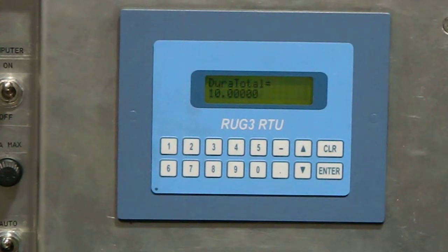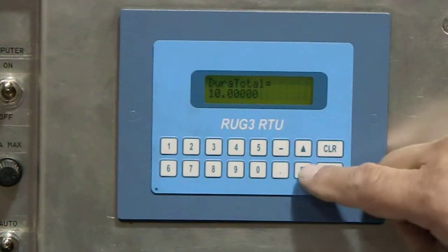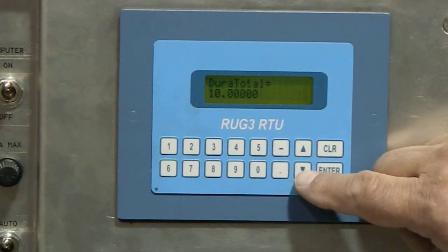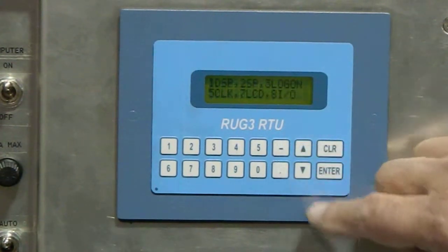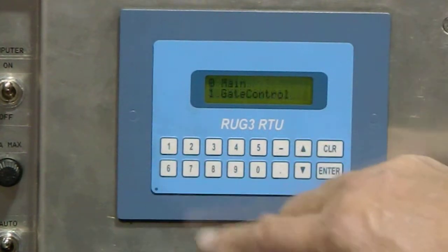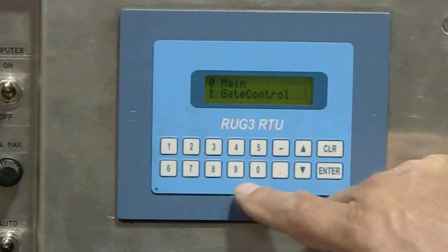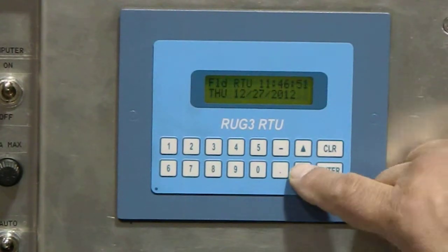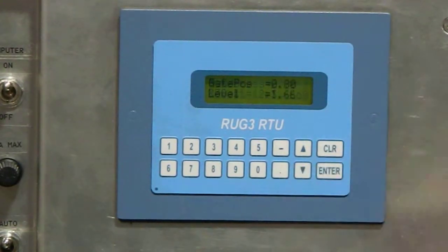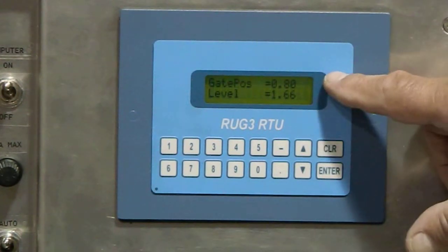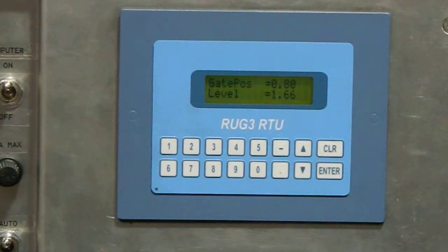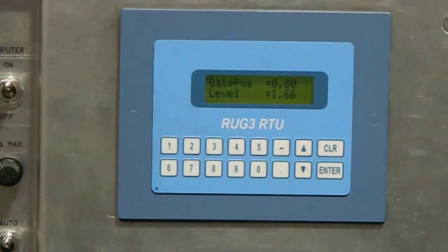Now, that's to give you 5 seconds of lag time. In most cases, it would be many more seconds than that to let the water adjust or to let whatever systems you have settle down before you want to make another adjustment. Minus gets you to the main menu. 1 gets you to the selection of screens. 0 gets you to the main screen. Go down 1, that tells you the address. And my favorite, what's the gate position now and what's the level on the sensor. Okay, so that tells you a little bit about the embedded RTU in the actuator.